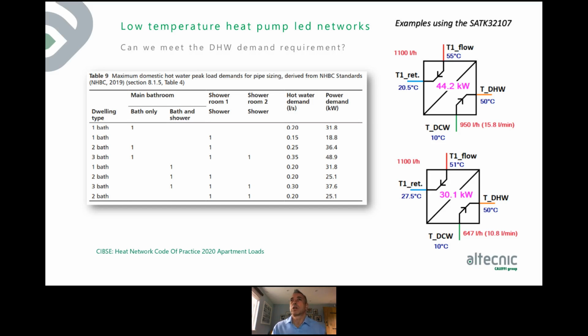But what happens if you start to lower that temperature? And here in the second calculation, we have 51 degrees C, so a lot lower. Now we're down to a 1 degree approach, not normally recommended, but you're down at a very low temperature, and you can see the output potential from the HRU drops to just 30 kilowatts. So we now miss some of the larger apartments here.